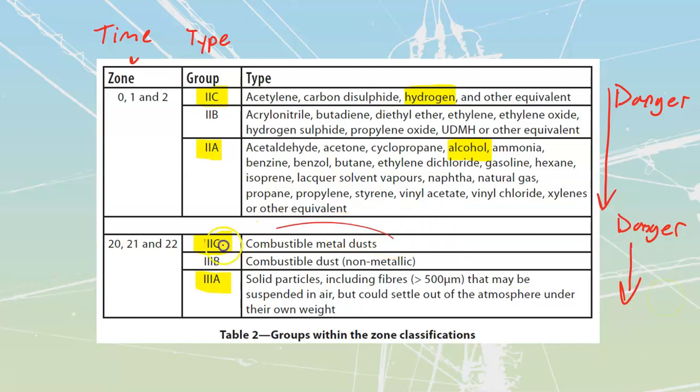Take a look at combustible metal dust. What does an arc burn at? Well, an arc is going to burn between 3,000 all the way up to 30,000 degrees. This is hotter than the surface of the sun. It's incredibly hot. So if I have suspended fine metal dust in the air, particularly things like magnesiums and aluminums, we can get an arc that travels through there, vaporizes across, and you end up with these massive explosions. So it's a really dangerous type of dust.